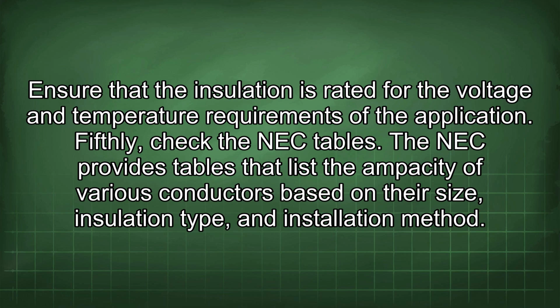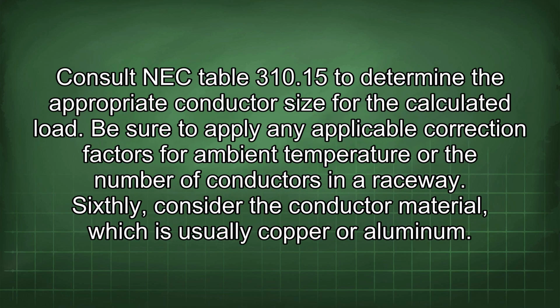Fifthly, check the NEC tables. The NEC provides tables that list the ampacity of various conductors based on their size, insulation type, and installation method. Consult NEC table 310.15 to determine the appropriate conductor size for the calculated load. Be sure to apply any applicable correction factors for ambient temperature or the number of conductors in a raceway.